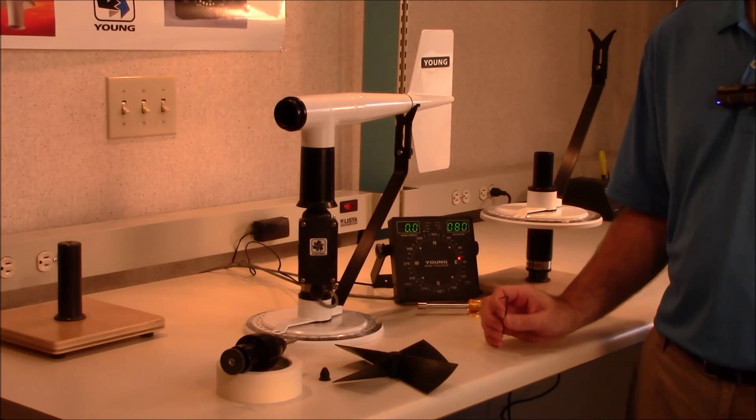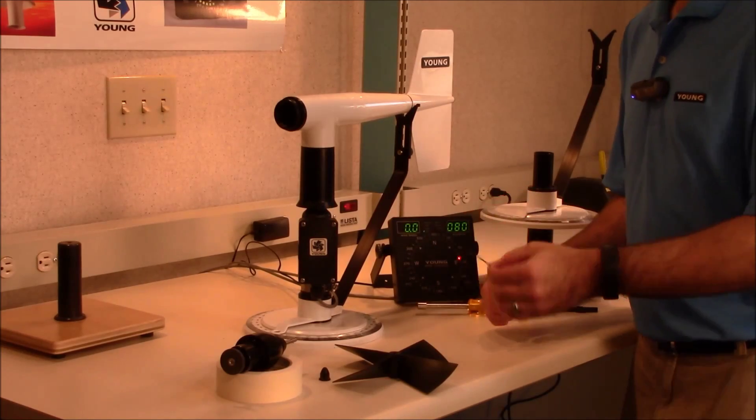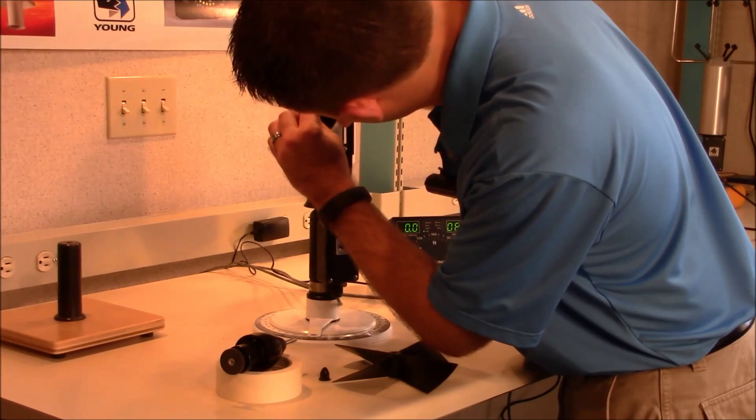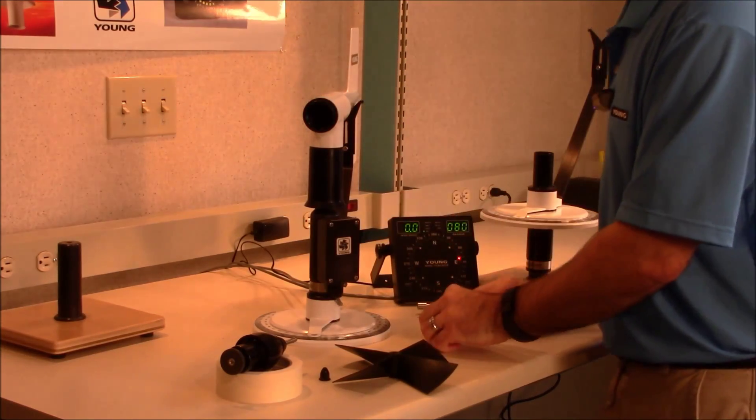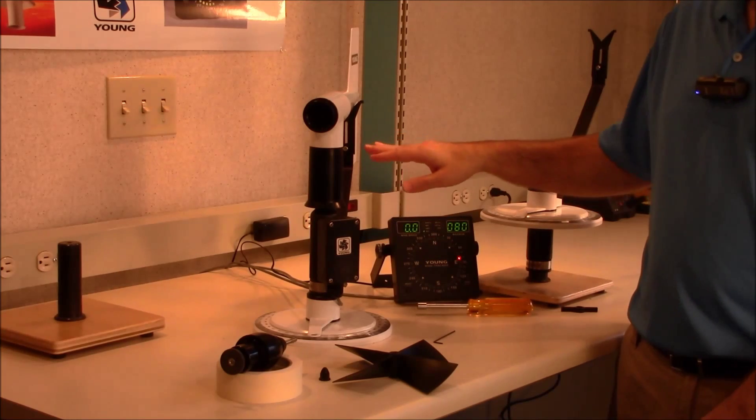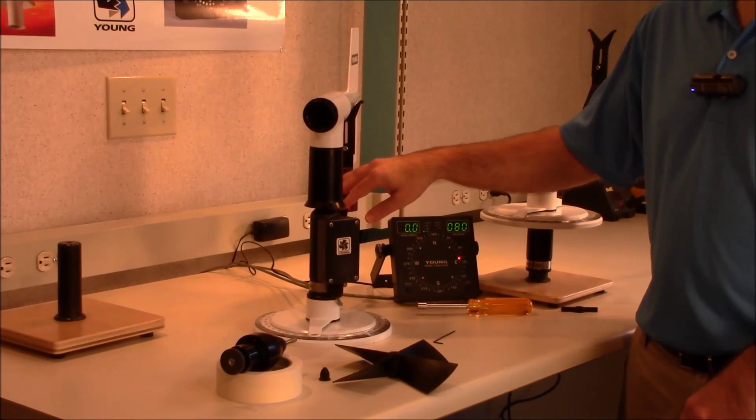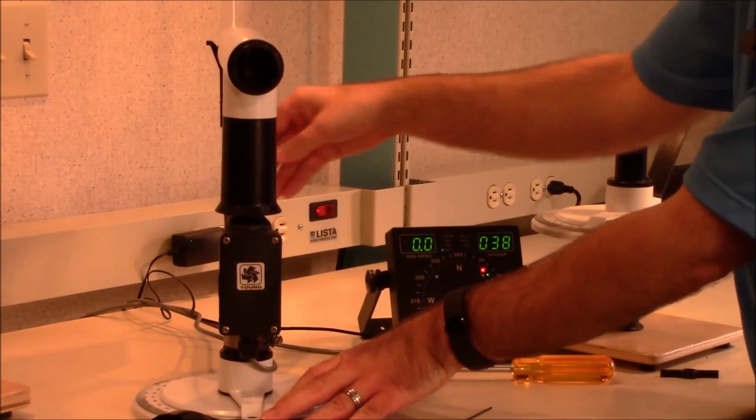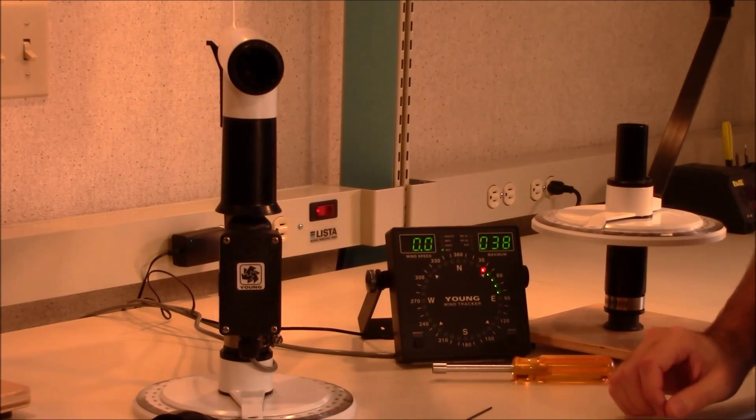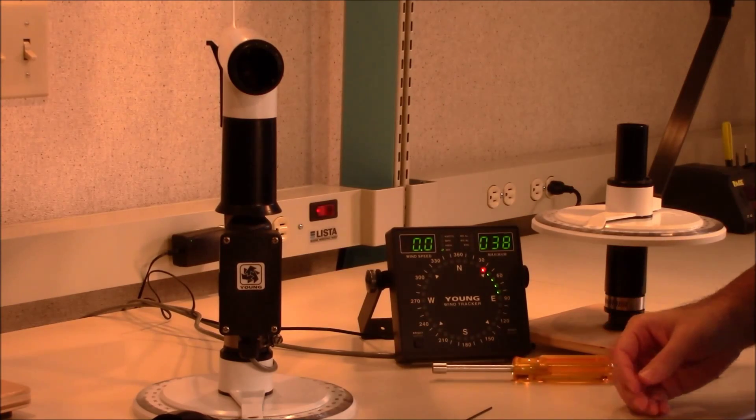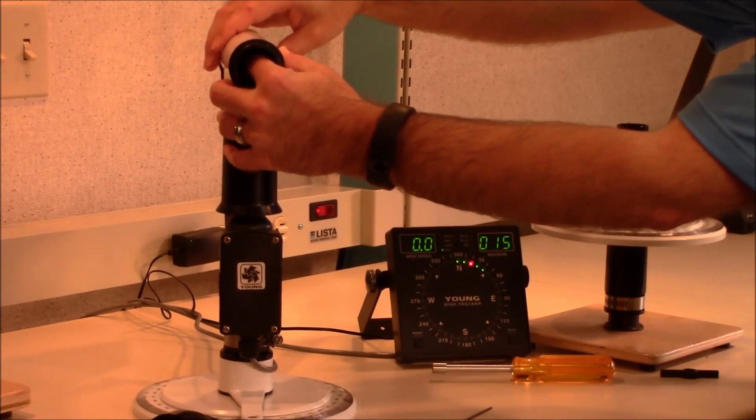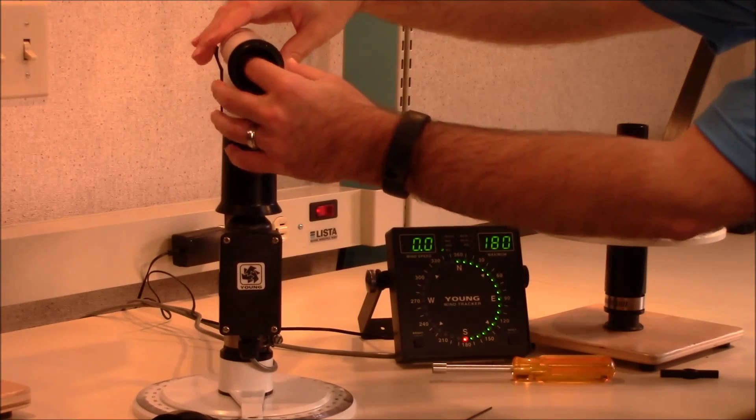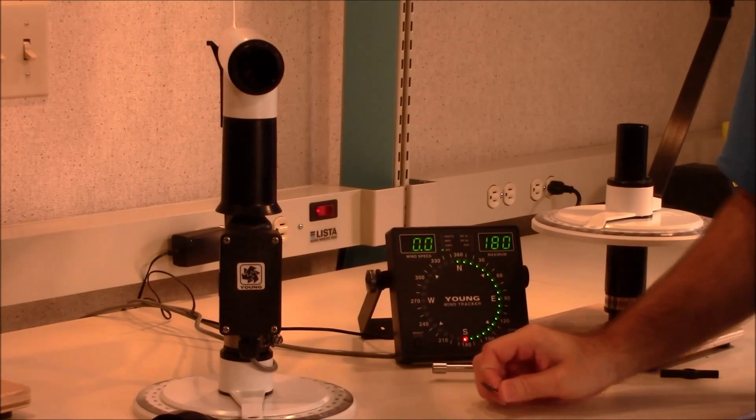First, we'll need to loosen the set screw in the coupling. Using your hex wrench, loosen that set screw a little bit. You'll need to turn the wind monitor to face 180 degrees, and then turn the thumb wheel until your display is reading 180 degrees. Now we can tighten the set screw again.